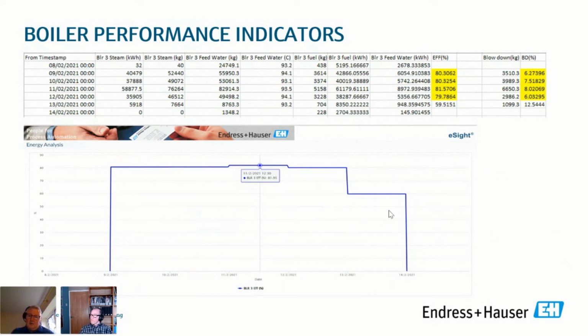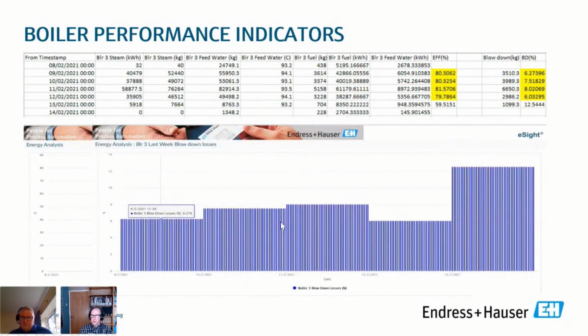But the blowdown percentages are amazing too. The impact they could potentially have if you're not tracking that could be huge. You really need to pay attention to blowdown. If you're spending a few million pounds a year on fuel going into your boilers, and you don't understand how the boilers are kicking in and what the load profile is on the site, you won't know what each fuel to steam efficiency is, and ultimately it all tracks back to good old kilowatt hours, what you're paying for.